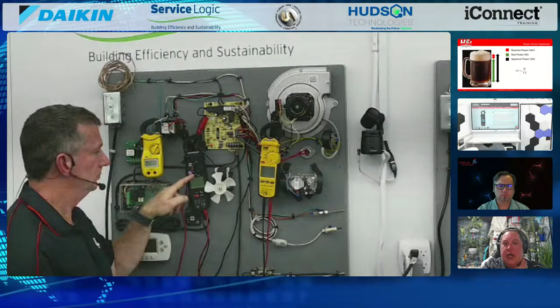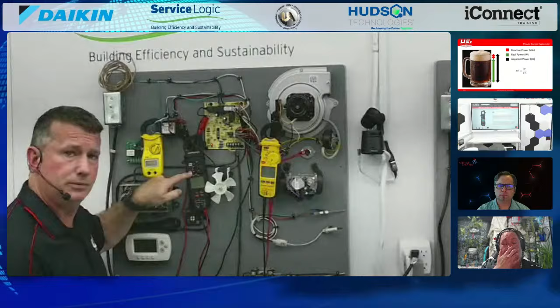When you look at the dial of the meter, you'll notice that when you go over to the volts, just to the left of it in red, you'll see the power factor and the watts. That's an indication - if it's in white on the face of our meter, that's the default mode. So turn it to volts, and you'll see there's a red select button on your meter that you'll have to press and hold. That red color coordinates to the functionality that you'll see on your screen. Once you press and hold it long enough, you'll see that your display screen will now start saying PF on one line and W on the other, giving you the power factor and the watts.